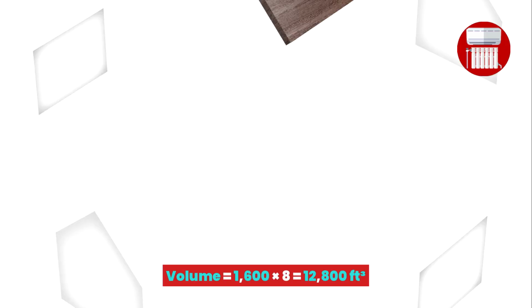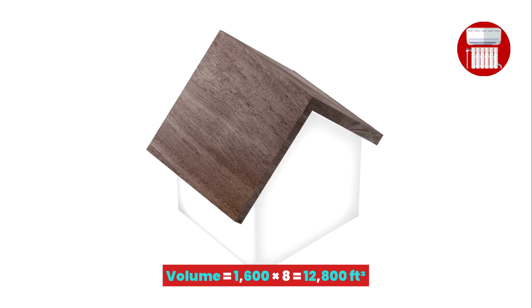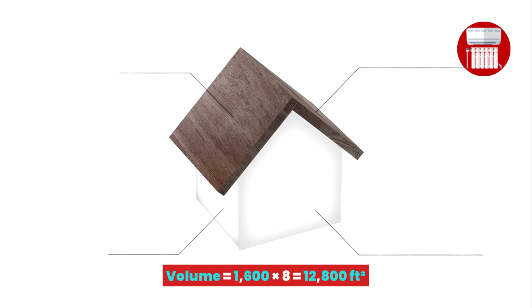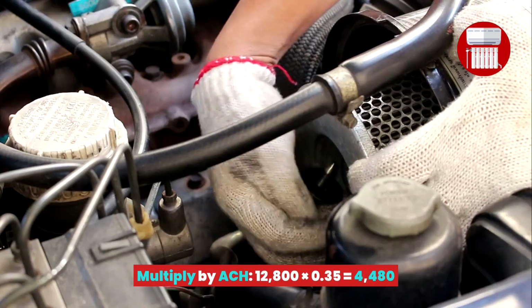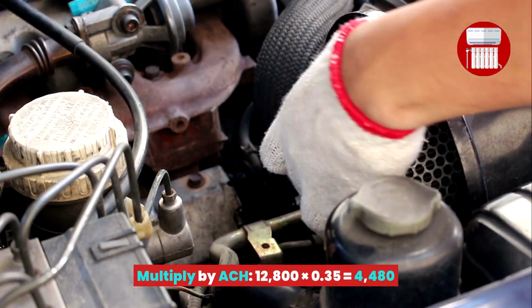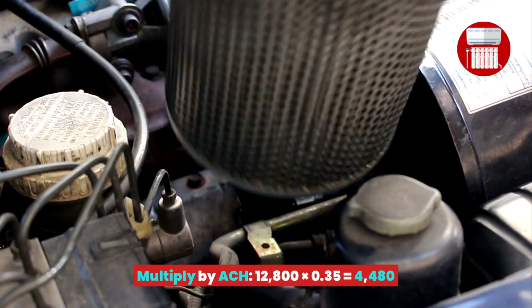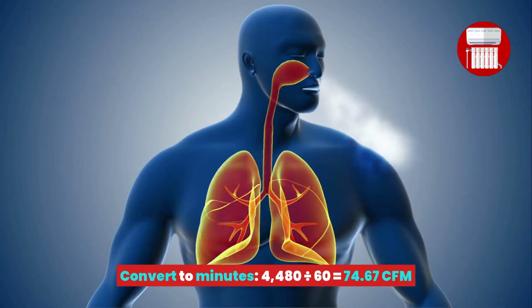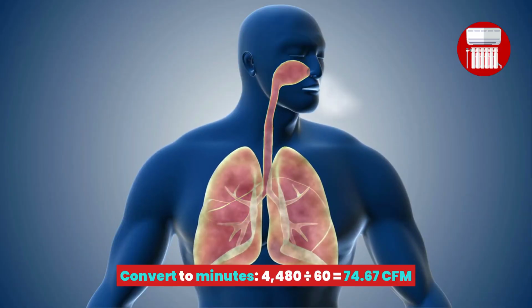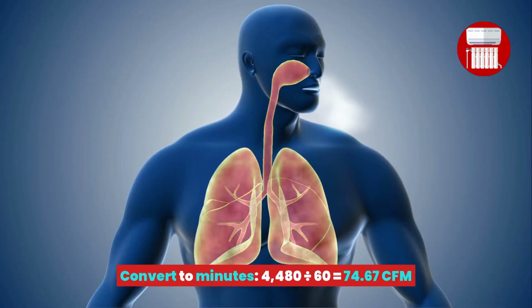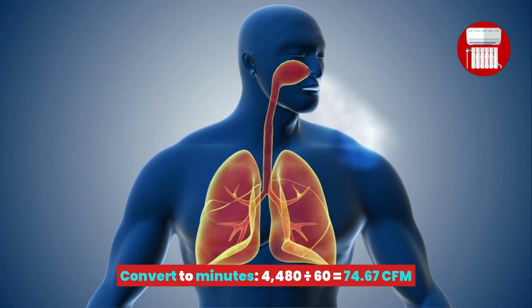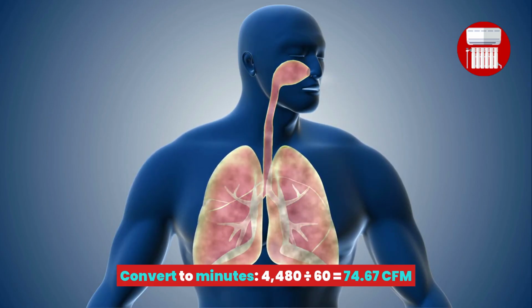Final recap. Volume: 1,600 times 8 equals 12,800 cubic feet. Multiply by ACH: 12,800 times 0.35 equals 4,480. Convert to minutes: 4,480 divided by 60 equals 74.67 CFM.